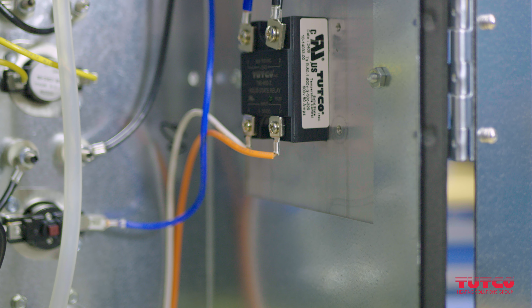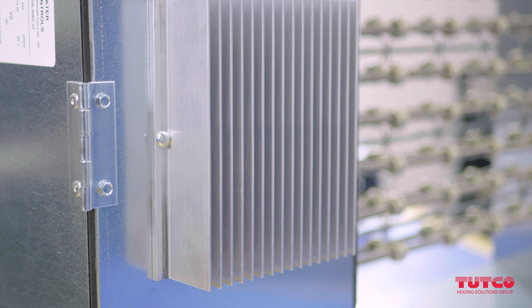Our system, we've already got a thermostat, and we're going to be providing a 24-volt signal. Is that going to interfere here? This heater is a SCR control, so that means it would need a 0 to 10 volt DC input, analog input, in order to operate. So my standard thermostat is not going to work for SCR. That's right. What you see on the wall here is called an SCR. Okay. It's mounted on a heat sink that protrudes to the outside of the heater, as you can see here. So what that does is allows the heater to modulate and maintain the perfect set point.